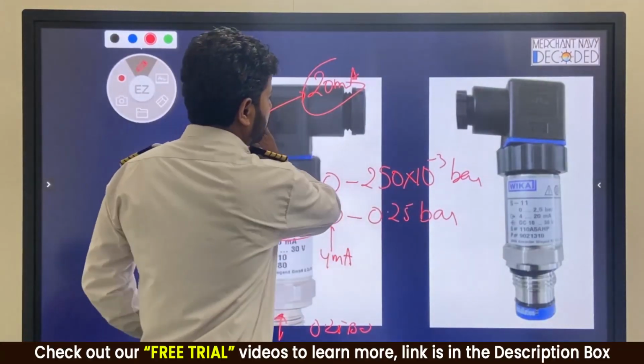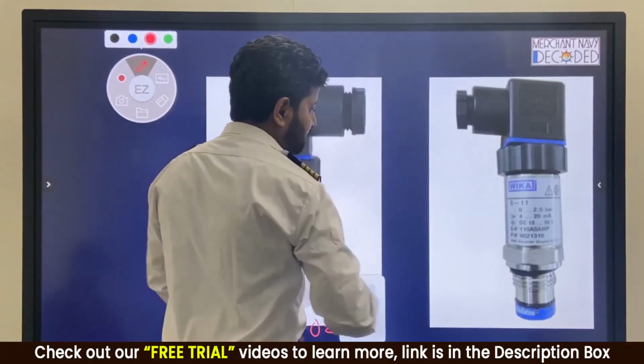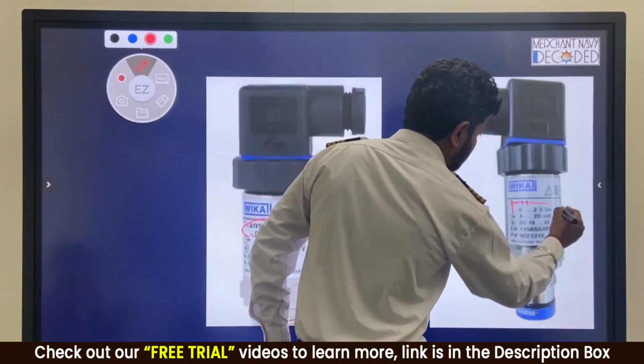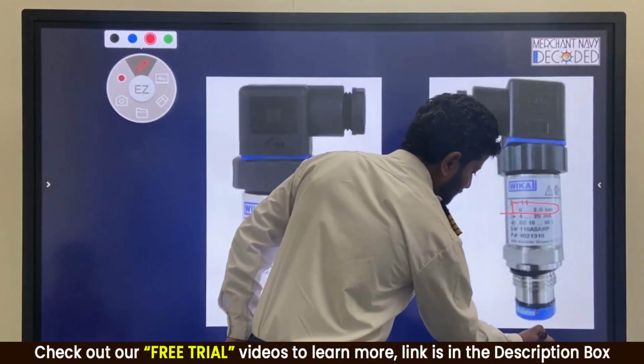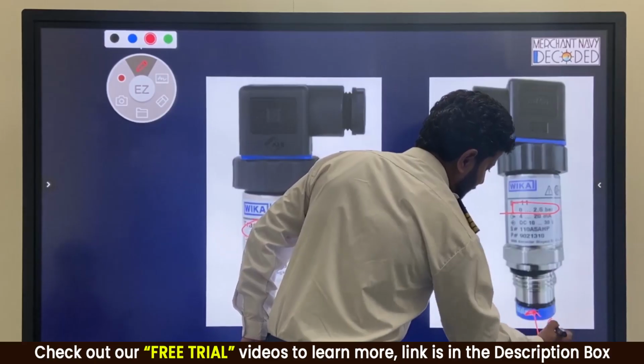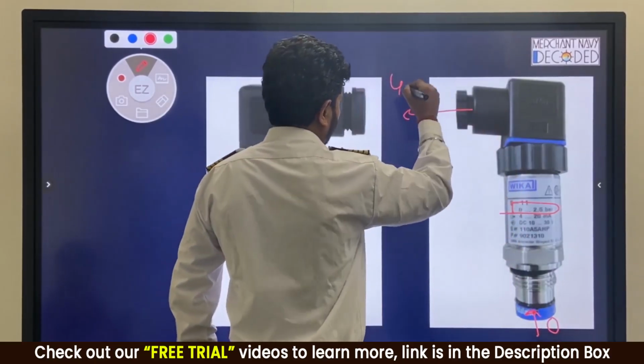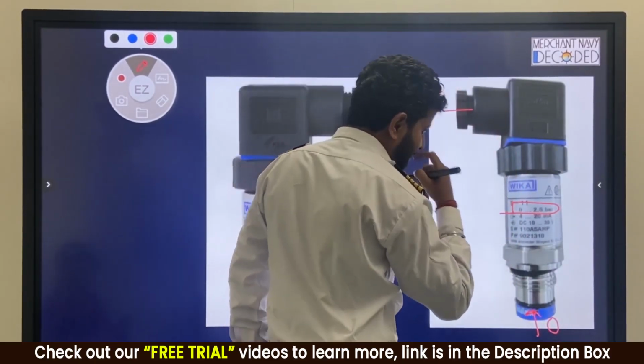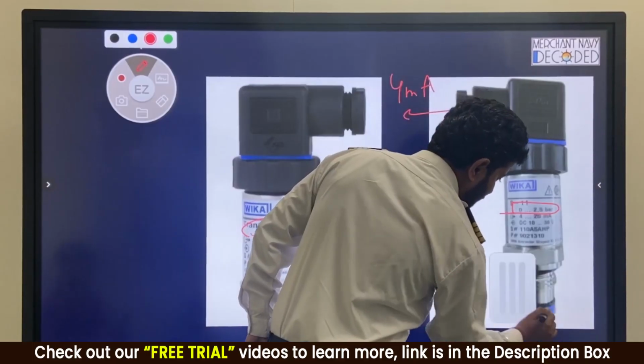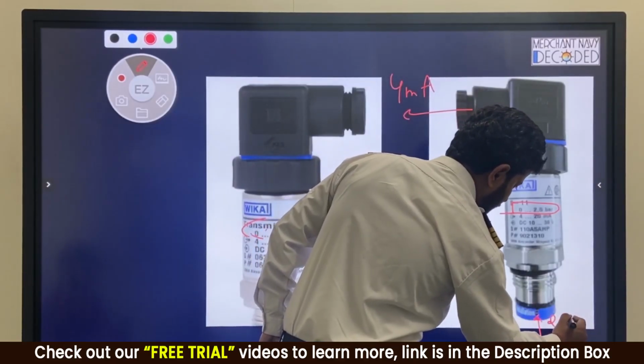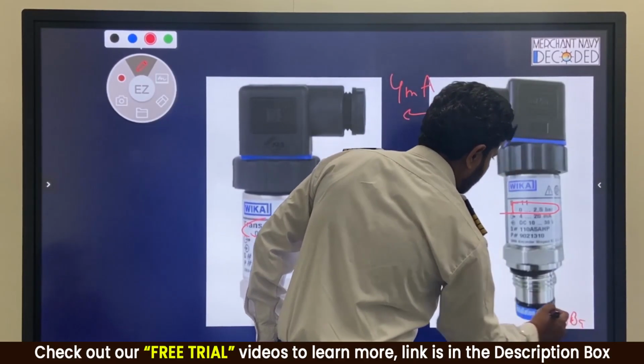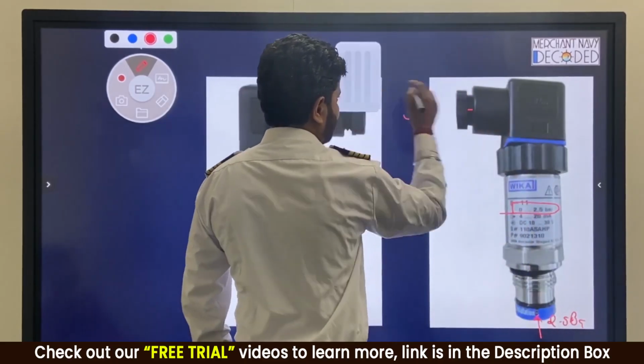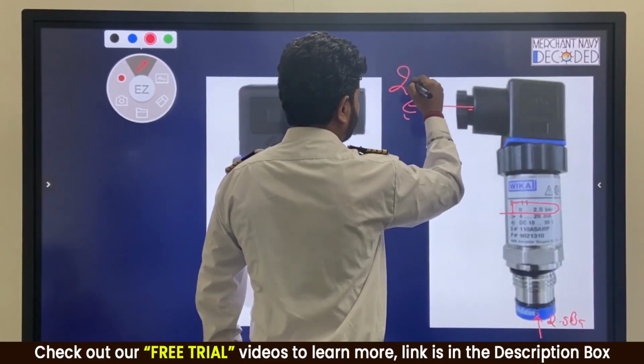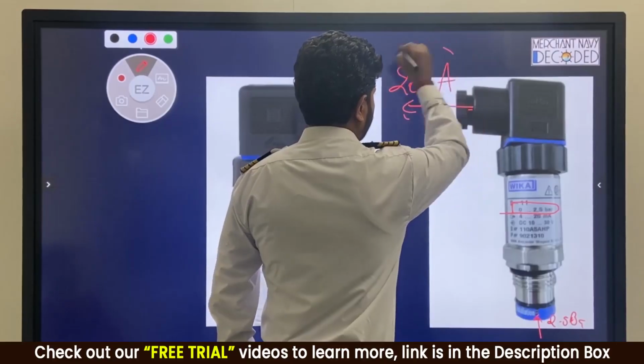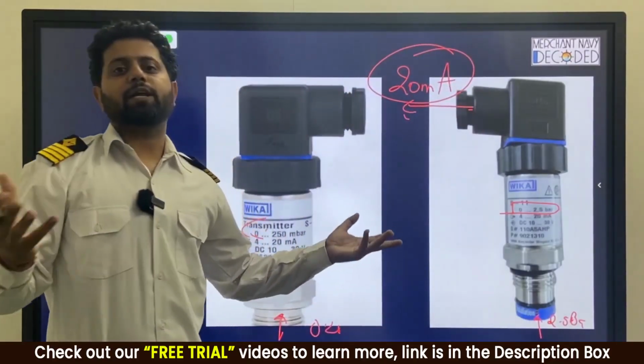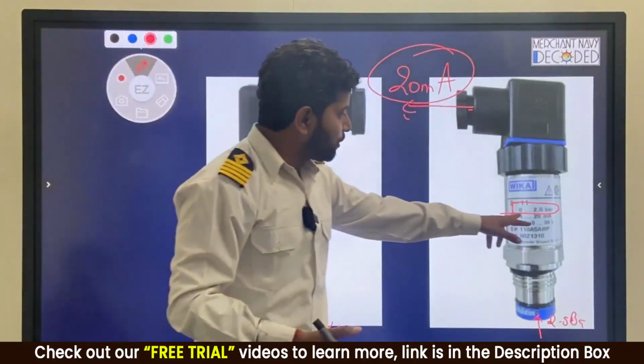On the other hand, can you see over here? I do not know whether it is visible. Over here, the range is given 0 to 2.5 bar. So when the pressure acting over here is 0 bar, the current will be 4 milliamps. When the pressure acting over here will be 2.5 bar, then the current output will be 20 milliamps, and in between the whole range is there. So this is what you have to see.